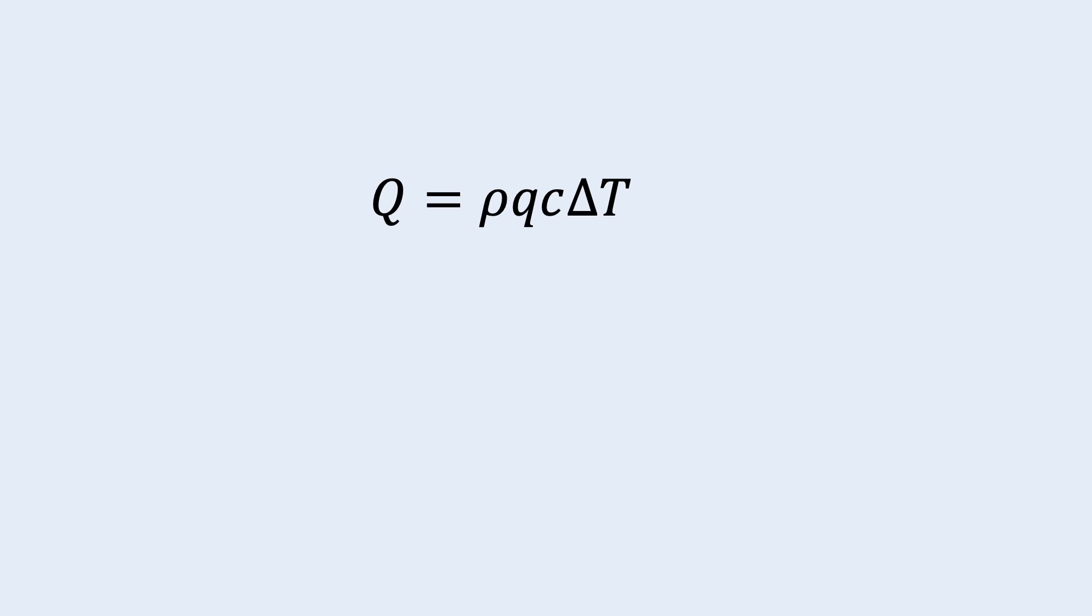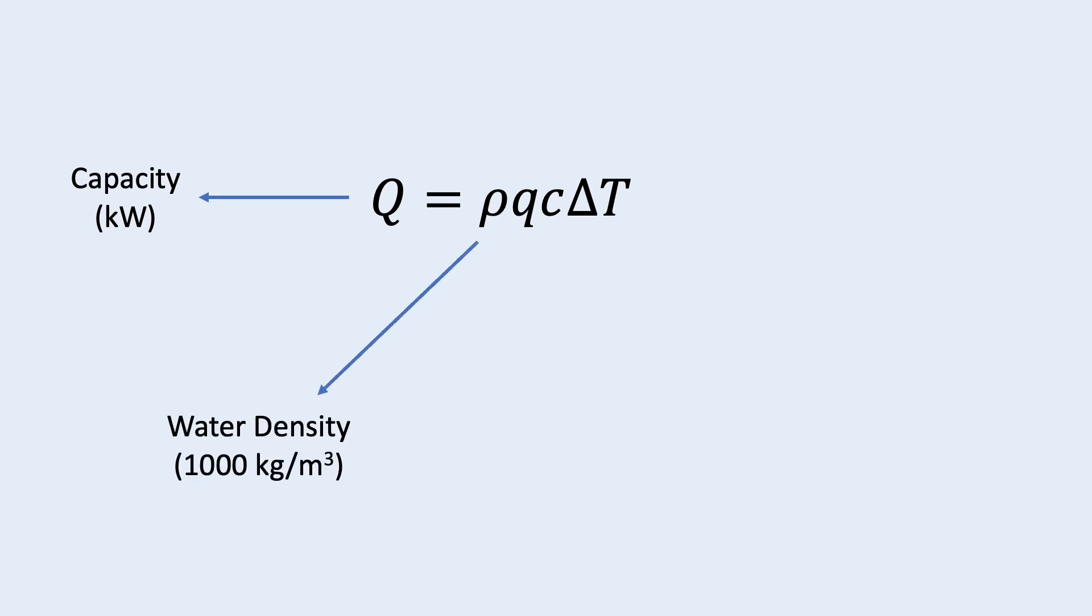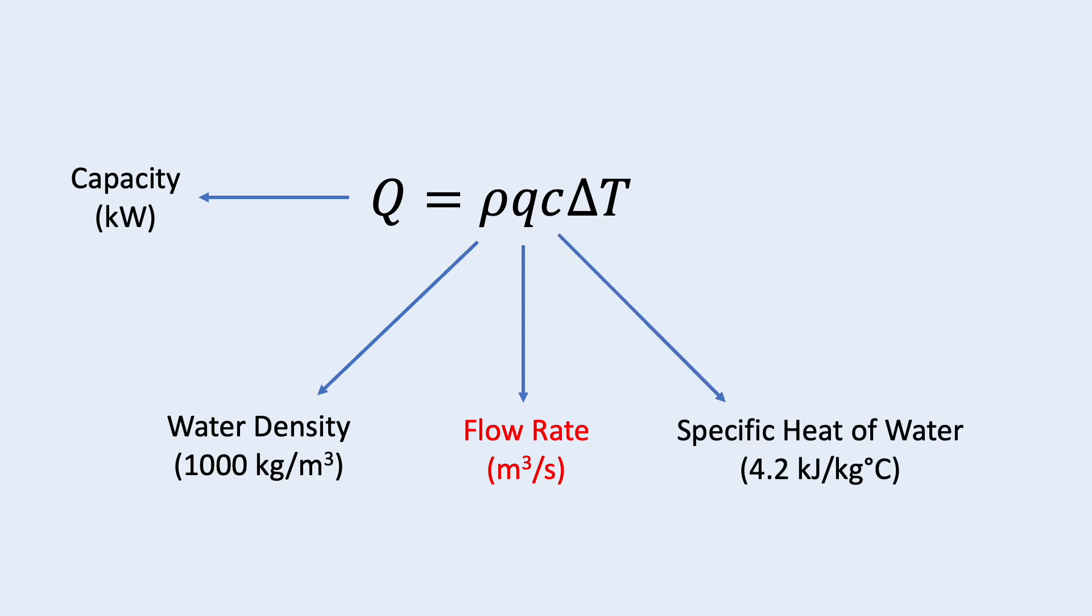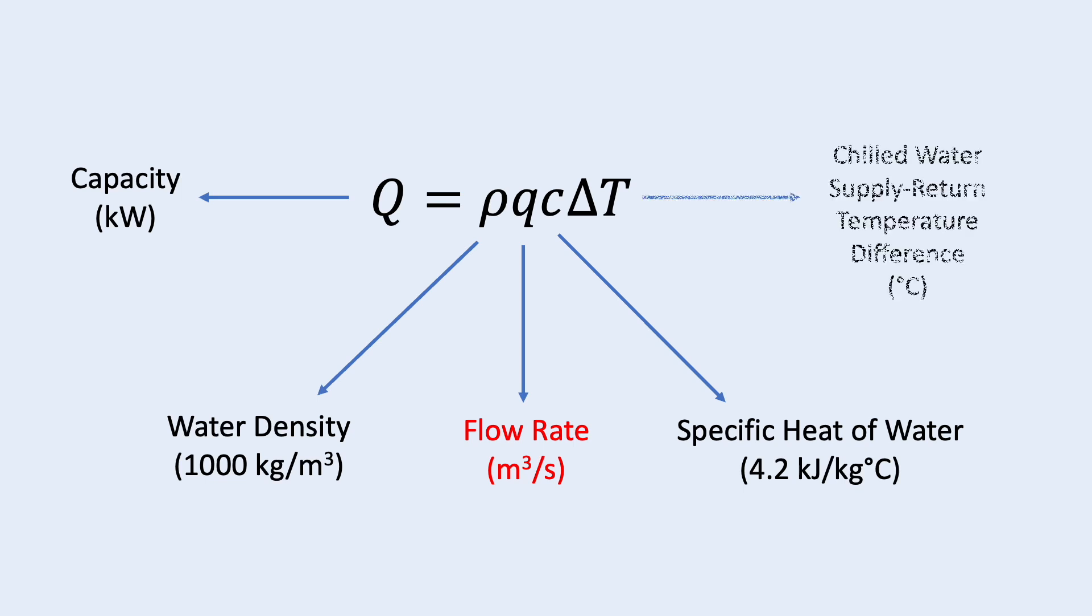Flow rate is calculated using the heat transfer equation. Q is the capacity in kilowatt. Rho is the density of water which is 1000 kg per meter cube. The small q is the flow rate in meter cube per second. C is the specific heat of water which is 4.2 kilojoule per kg°C. Delta T is the difference between the chilled water supply and return temperature.